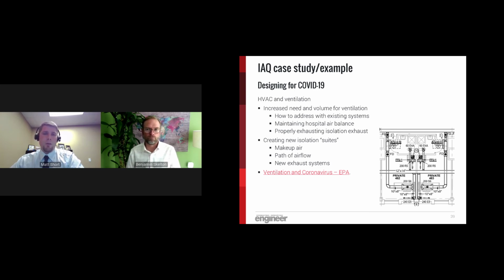So in this case, a new outside air handling unit was provided to pre-treat outside air and serve the spaces with makeup air. Additionally, fan filter units were installed in a vertical chase to provide HEPA filtration and help achieve the room's newly required air changes per hour. As you can see, the patient rooms after this renovation are negative to the adjacent staff corridor to ensure all air from the space is exhausted to the exterior of the building. Now, Benny, I think we'll discuss further requirements in a commercial type setting.